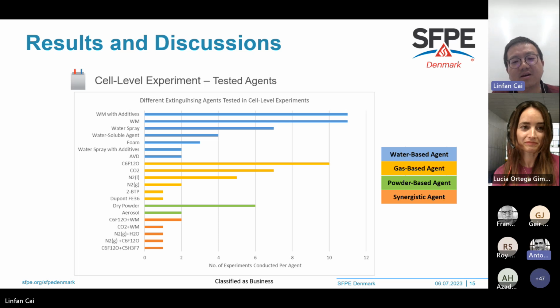The battery manufacturers need to advise what kind of fire load comes from their single battery rack, so the fire suppression manufacturer can design the appropriate size of the suppression system accordingly. I didn't find any formula or correlation between the capacity of the extinguishing agent versus the type of protected area, so this will need some design coordination later in real applications. Thank you.